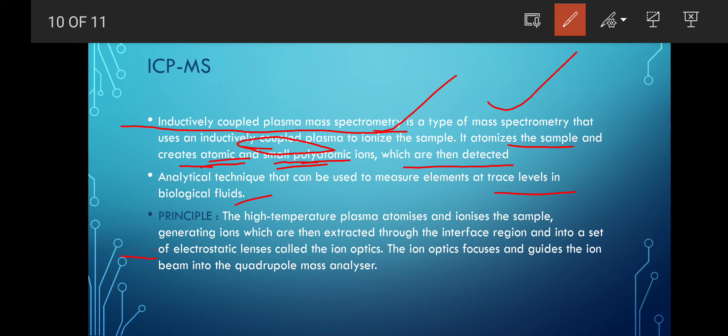The principle is that the high temperature plasma atomizes and ionizes the sample, generating ions which are extracted through an interface region. They are extracted and then guided into electrostatic lenses called ion optics. The ion optics focus and guide the ion beam into the quadrupole mass analyzer. This is the analyzer.